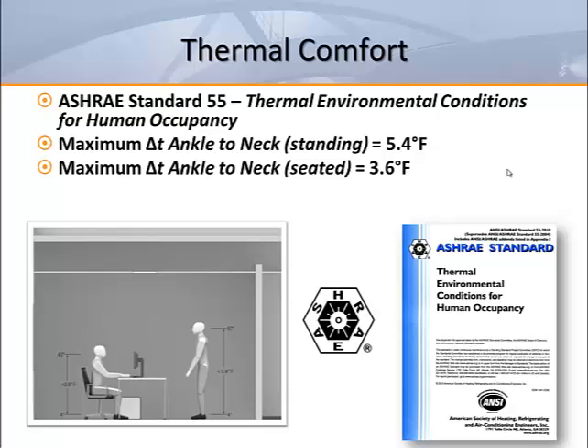ASHRAE Standard 55 also recommends that for good thermal comfort, the temperature difference between the ankle and neck level of a standing person should not exceed 5.4 degrees Fahrenheit. For a seated occupant, the temperature difference should be no more than 3.6 degrees Fahrenheit. This equates to about 1 degree Fahrenheit per foot of rise throughout the occupied area.